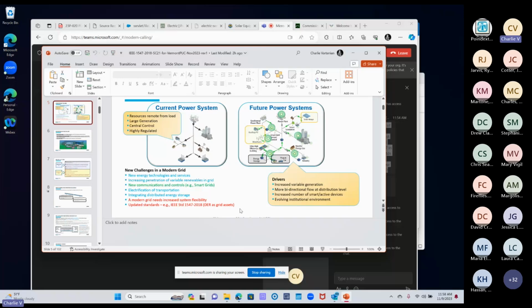Irika has a really good summary of that - I'll see if I can find a link and put it in the chat. But the vast majority - again, jurisdiction is for those regulated by a state PUC, primarily investor-owned utilities - it's very ubiquitous that 1547 is adopted, but typically with exceptions. The big one being galvanic isolation, a lockable visible disconnect switch. So in my experience, that's the big addition that a lot of states will add within their specific jurisdictional tariff rules that goes above and beyond 1547.